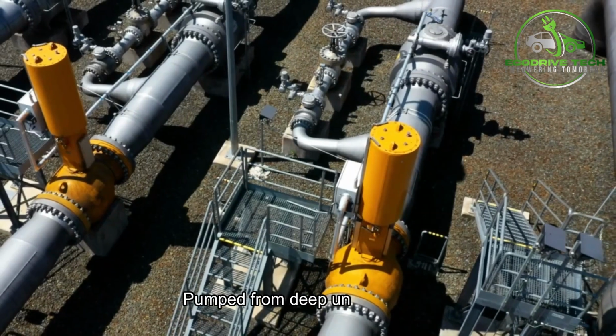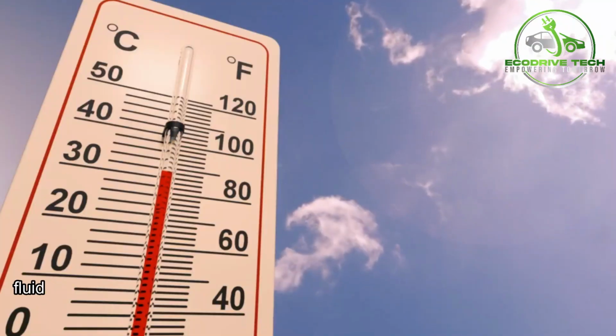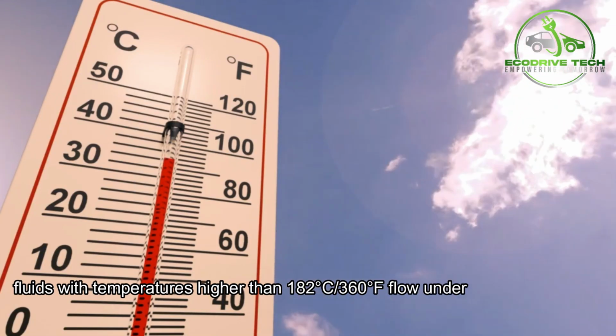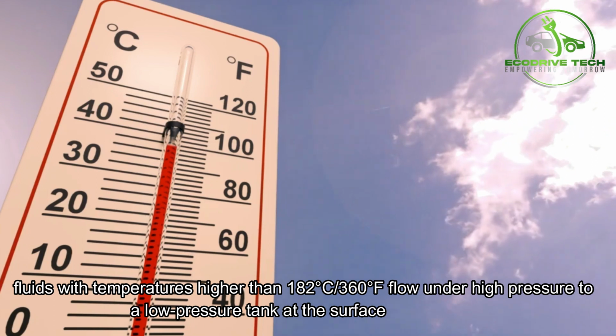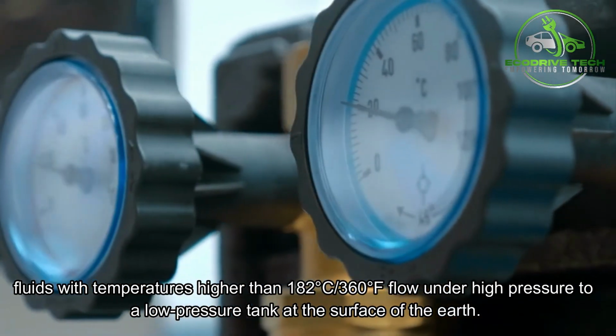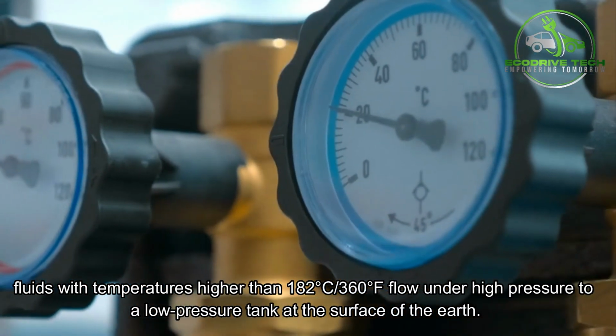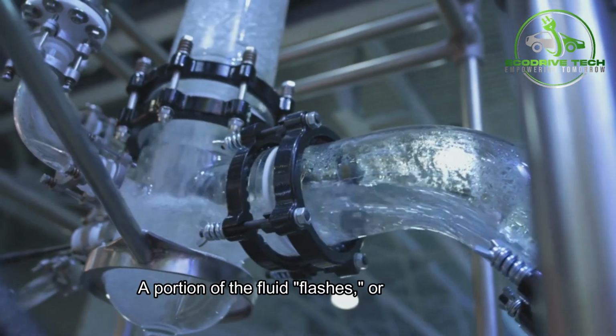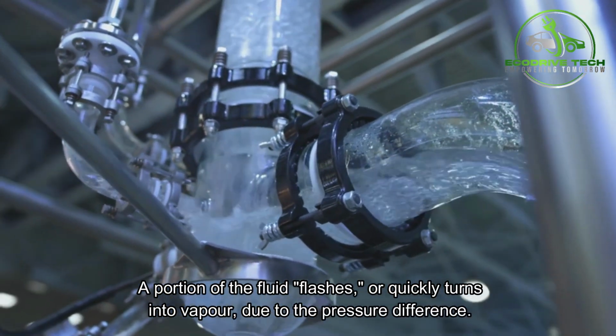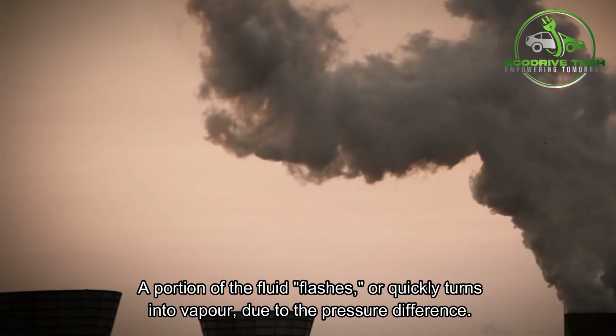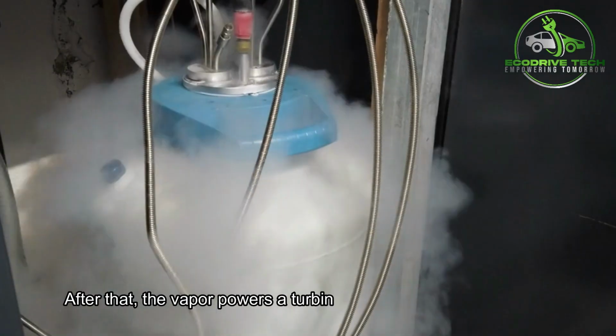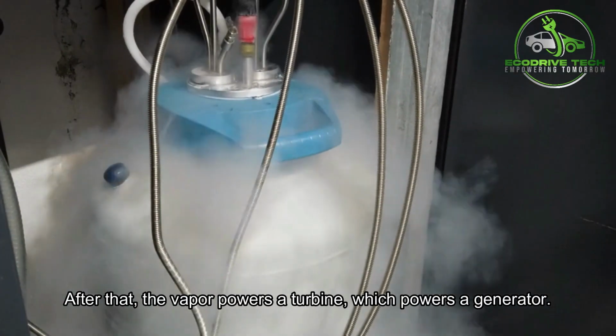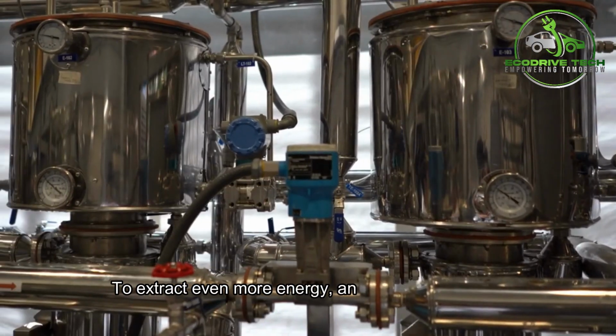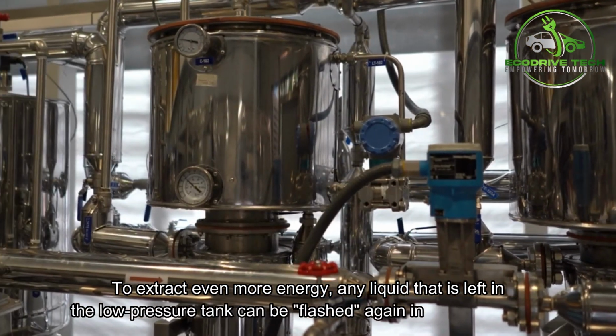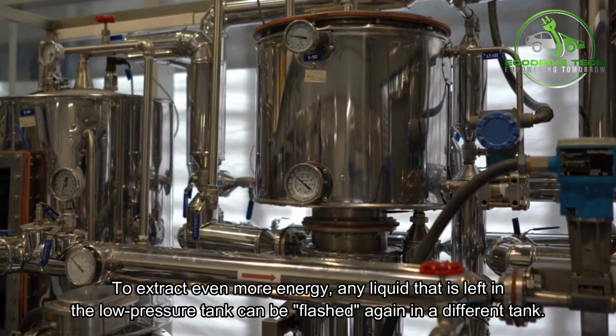Pumped from deep underground, fluids with temperatures higher than 182 degrees Celsius / 360 degrees Fahrenheit flow under high pressure to a low-pressure tank at the surface of the Earth. A portion of the fluid flashes, or quickly turns into vapor, due to the pressure difference. After that, the vapor powers a turbine, which powers a generator. To extract even more energy, any liquid that is left in a low-pressure tank can be flashed again in a different tank.